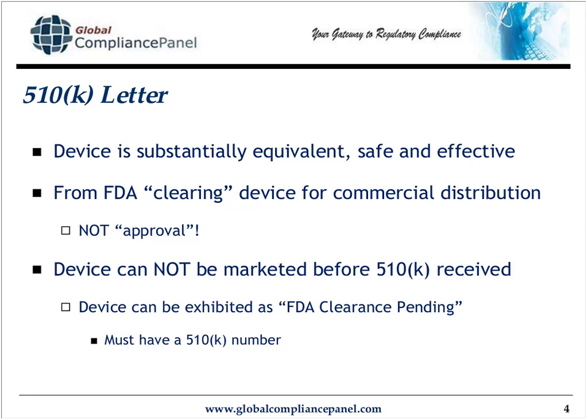Interestingly enough, your device cannot be marketed before the 510K is received. It's not very interesting. It's obvious. However, there is a slight area that the agency gives us. If you have submitted your 510K and you have received a notification that says, well, hey, thanks for your 510K, here's a number, you'll hear from us sometime in the future, once you receive a 510K number at a trade show, you can exhibit your device as FDA clearance, remember not approval but clearance, pending.